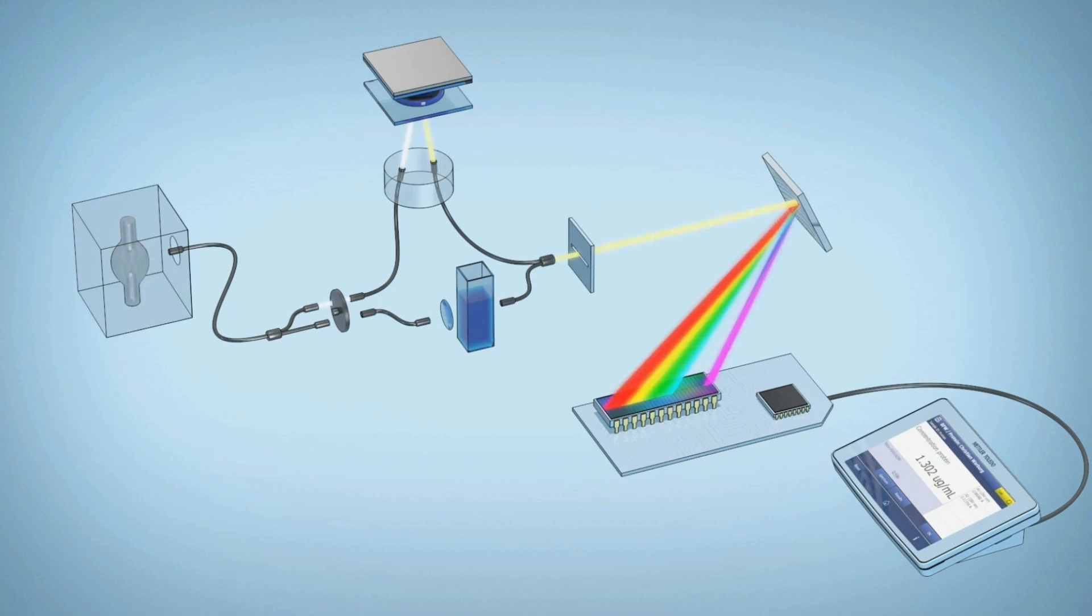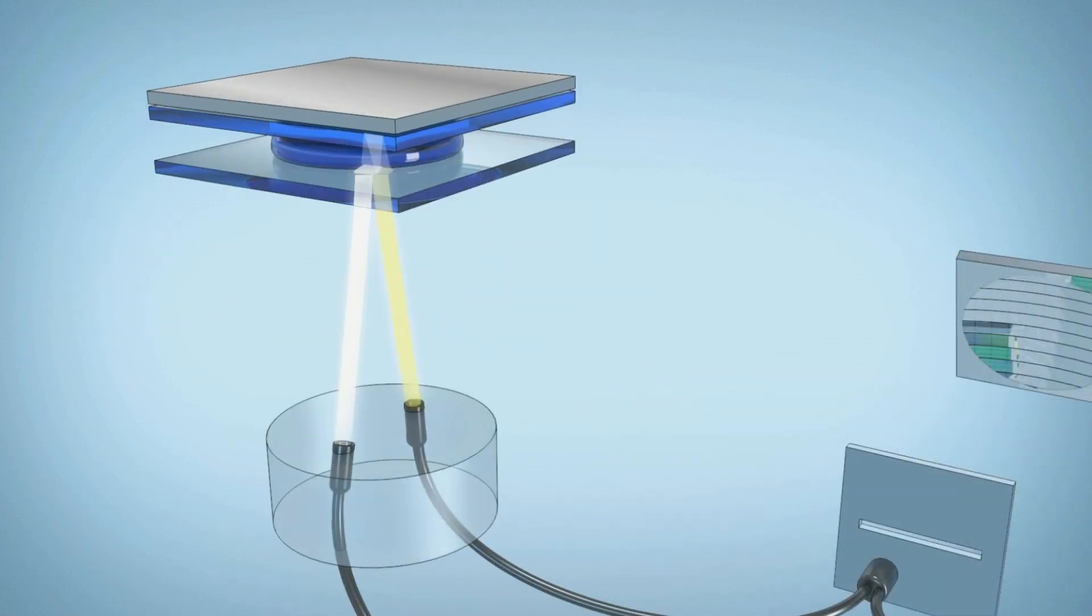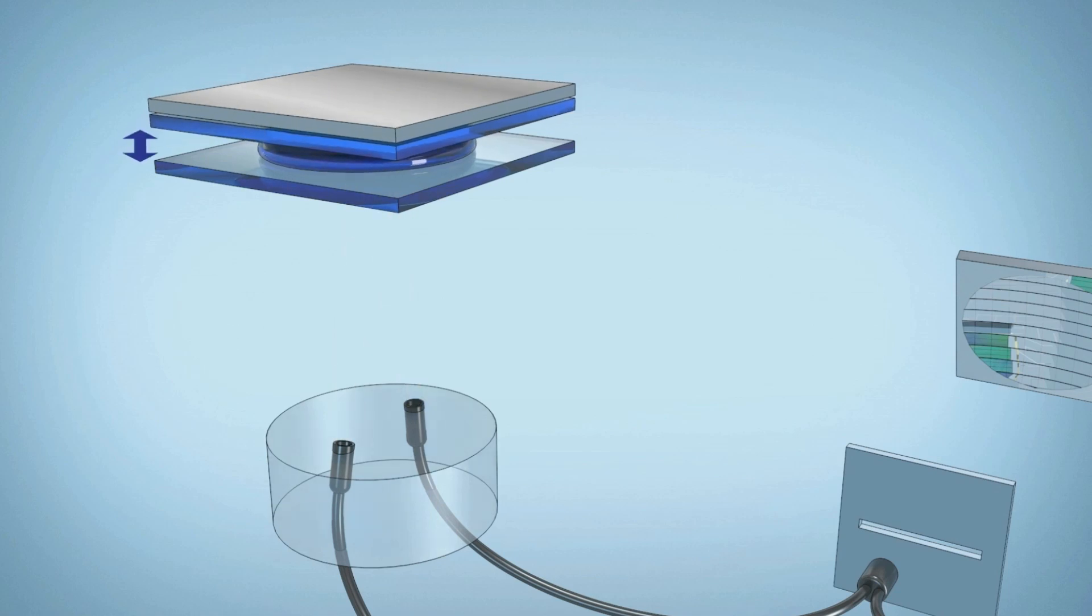This time, the light can go through the cuvette as before, or be diverted to the micro-volume platform, as you can see in this video. Lock path technology within the arm of the UV5 nano allows a fixed path length of either 1mm or 0.1mm to be maintained.